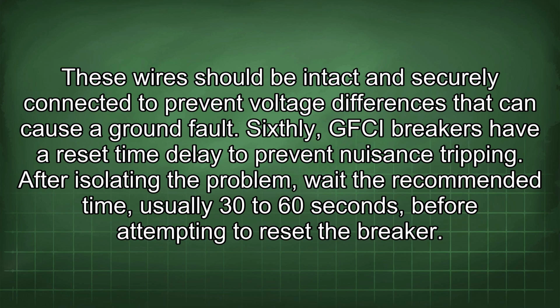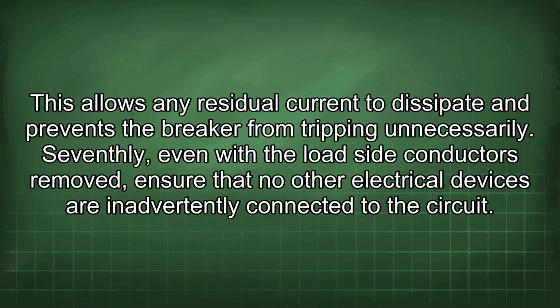Sixthly, GFCI breakers have a reset time delay to prevent nuisance tripping. After isolating the problem, wait the recommended time, usually 30 to 60 seconds, before attempting to reset the breaker. This allows any residual current to dissipate and prevents the breaker from tripping unnecessarily.